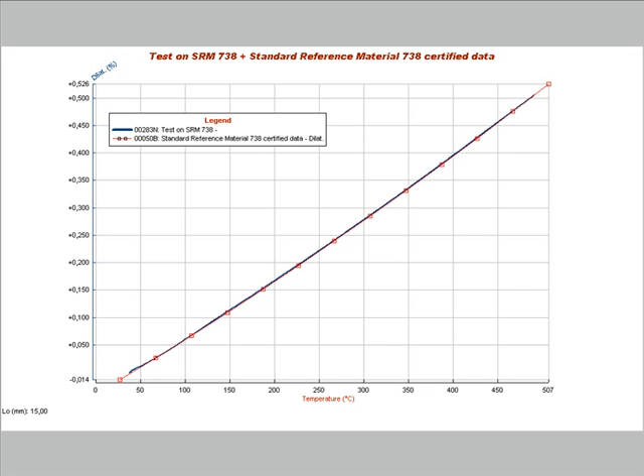The blue curve in this graph is the actual measurement on a standard material supplied by the National Institute for Standards and Technologies, while the red dotted curve is the plot of the data certified by NIST. There is a perfect match with no correction applied.